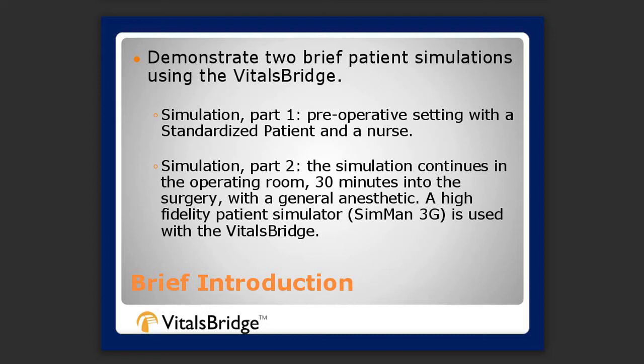A question has come in: how long has the Vitals Bridge been on the market? The Vitals Bridge has been used in VA hospitals for two years and has been sold exclusively by Laerdal. Many improvements have been made — for example, it used to require a modification to the mannequin for pulse ox, but that's no longer the case as it's now built right into the pulse ox probe. Because of demand, it is now being taken to regular hospitals and simulation labs across the country, and soon internationally.